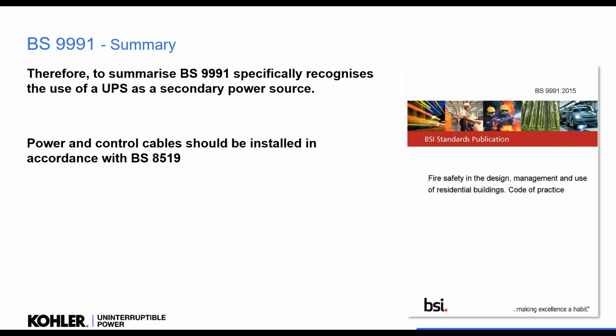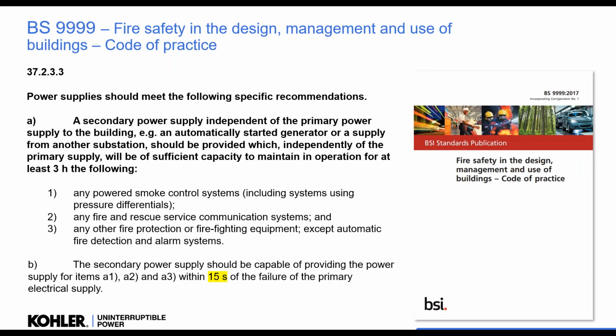9991 specifically says yes, you can use a UPS, but it does say refer to 8519 for guidance. Understandable. Okay, 9999 hasn't been updated recently, and it talks about a secondary power supply, for example, an automatically started generator or supply from another substation. It must be of sufficient capacity to maintain in operation for at least 3 hours all the smoke extract, the fire rescue comms, and other fire protection equipment. Okay, and it should be available within 15 seconds.